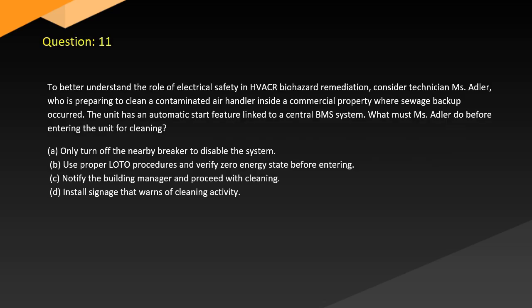Question 11. To better understand the role of electrical safety in HVAC biohazard remediation, consider a technician, Adler, who is preparing to clean a contaminated air handler inside a commercial property where a sewage backup occurred. The unit has an automatic start feature linked to a central BMS system. What must Adler do before entering the unit for cleaning? A. Only turn off the nearby breaker to disable the system. B. Use proper LOTO procedures and verify zero energy state before entering. C. Notify the building manager and proceed with cleaning. D. Install signage that warns of cleaning activity.